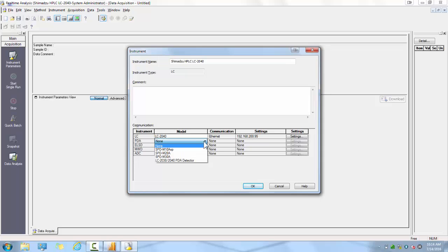If you have a photodiode array detector, you will then select which model you have from the drop-down menu here. If it is a modular PDA, such as an SPD-M20A or an M30A, you will need to click on the settings and select the PDA from the list, just as we did with the LC system.